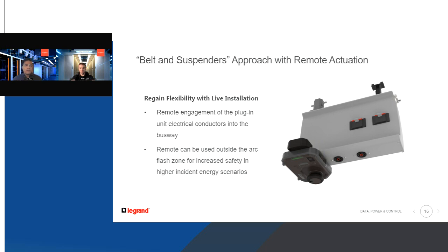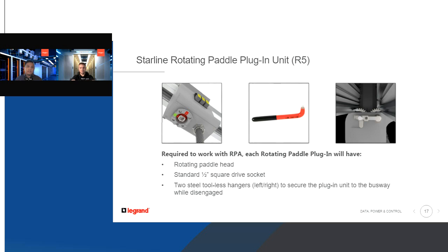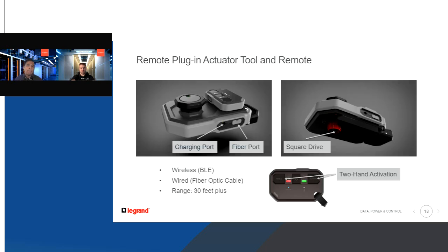How do we do that? We do that with a couple of mechanisms and modifications to the plugin itself. The first modification is a rotating paddle head, which you're seeing on the left, driven from a 1/2-inch square drive. The image on the left shows the receptacle in that 1/2-inch square drive. That allows us to rotate the paddle to engage and disengage it from the busway. Coupled with the two toolless hangers on the left and the right, the plugin can be mounted to the busway without engaging any of the electrical conductors. Once that plugin is installed into the busway, you install the remote actuator to the bottom of that plugin.